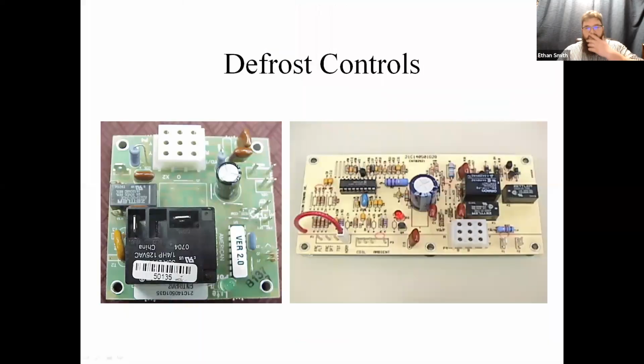But a couple of things you'll see on these defrost controls is we'll have our sensor inputs. So we're always going to have an ambient sensor and a coil sensor in the modern defrost controls. On the old ones, they were down here. New ones, they're pinned right here. It is a little tough to see on these things, but these are actually a set of test terminals that we got with the defrost controls. So there's my test common, and then I can force defrost or force the defrost to terminate by shorting those terminals together. And that will actually force the unit to defrost whether it needs it or not. This comes in handy if you've got an excessively frozen coil, had a roof dripping on it or something like that. You can force it to defrost repeatedly and clear that coil.